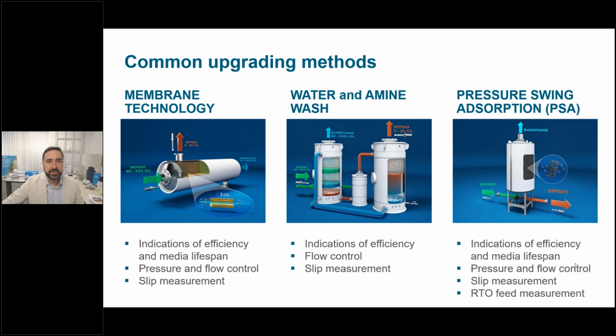Where slip measurement has value is both in the accounting for that methane amount, as well as making sure that too high methane concentrations are not sent to that RTO, which can overheat. Real-time measurement of the RTO feed can prevent damage and shutdowns. Next.